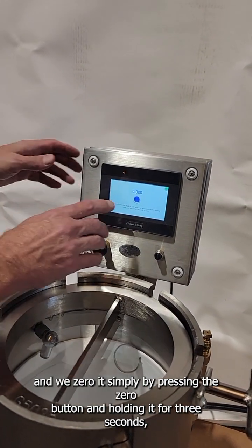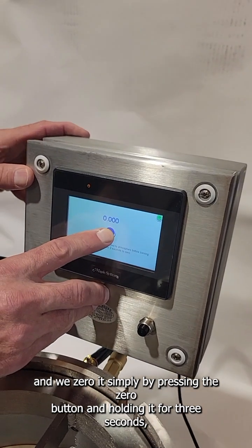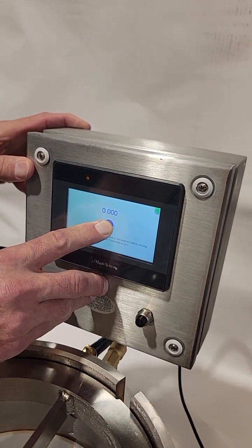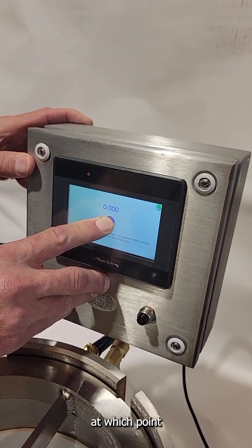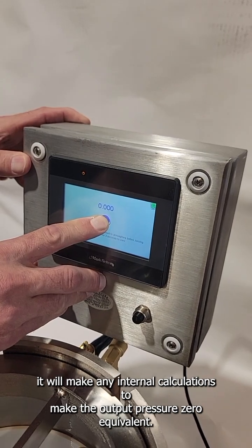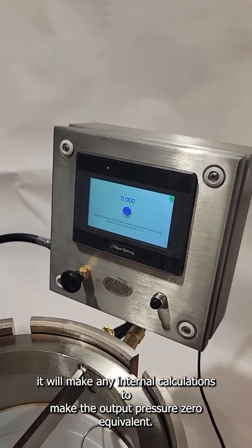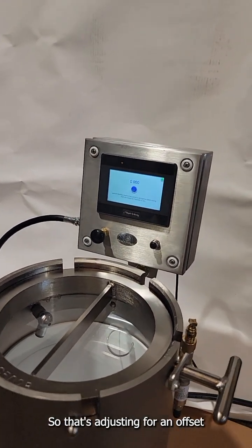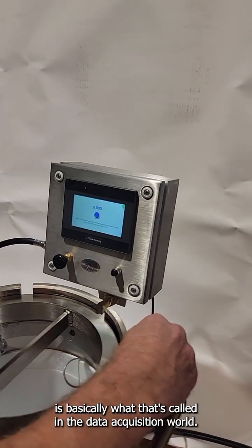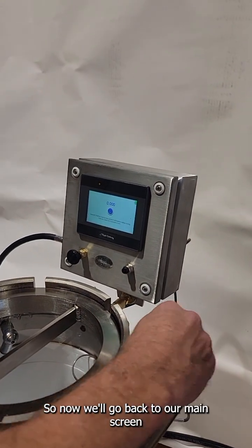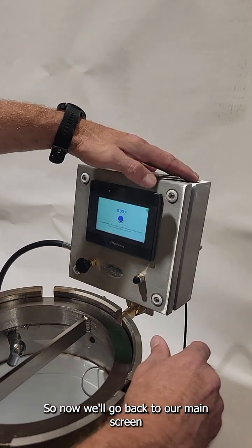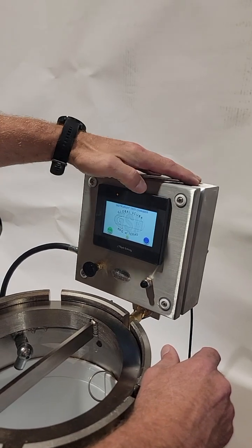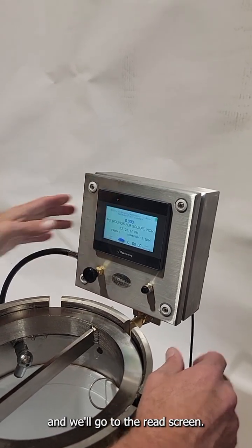We zero it simply by pressing the zero button and holding it for 3 seconds, at which point it will make any internal calculations to make the output pressure zero equivalent. That's adjusting for an offset, which is basically what that's called in the data acquisition world. So now we go back to our main screen and we go to the read screen.